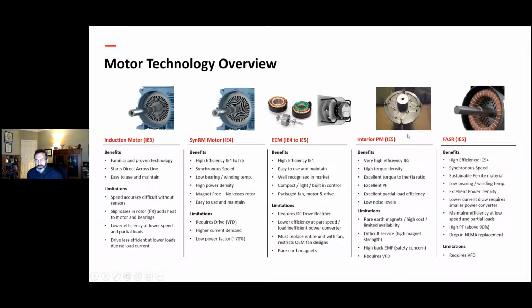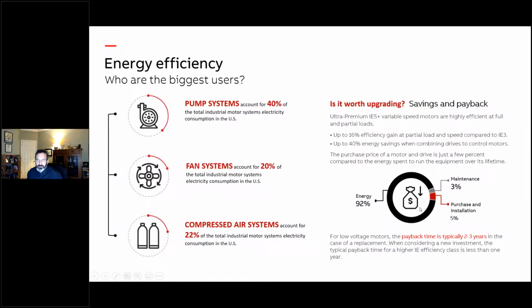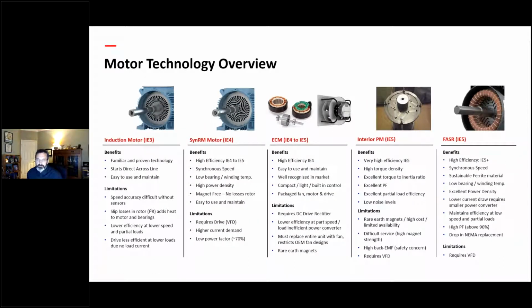The advantage of an interior PM motor with a rare earth magnet is it's probably the most efficient motor you can get. It has really high torque density, excellent torque to inertia ratio, high power factor, really good partial load efficiency and low noise levels. And then you're probably like, well, why isn't everybody using these in HVAC applications? Well, they're really high cost. They're difficult to service because the magnets are extremely strong, and they have high back EMF voltage. Basically, when you drive them in reverse, they turn into a generator. And because the magnets are so strong, they generate a lot of voltage, and that can be a safety concern. And they're really expensive. I mean, they're cost effective when you get like 30 horsepower and up.